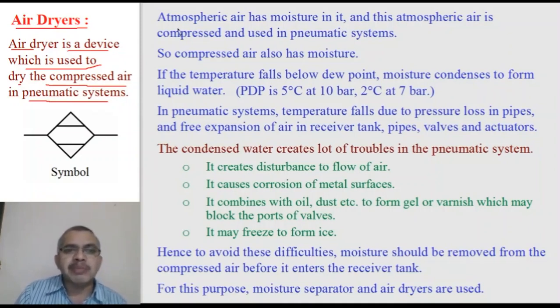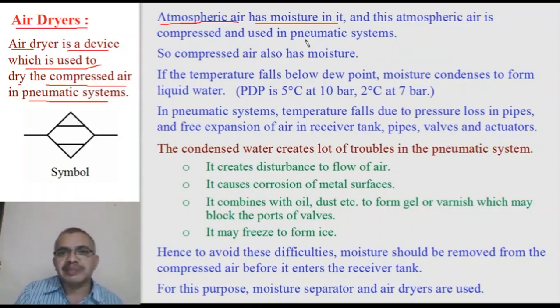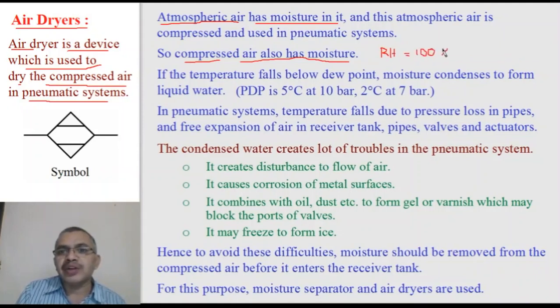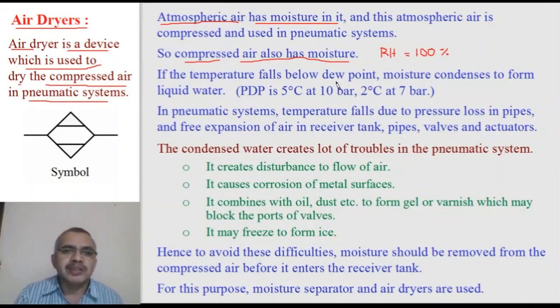The atmospheric air drawn by the compressor contains moisture. When the compressor draws that moist atmospheric air, moisture is also taken into the compressor, and hence the compressed air contains moisture. The relative humidity (RH) of compressed air is 100%, because the air is compressed and that compressed air contains more moisture — the moisture also gets compressed.